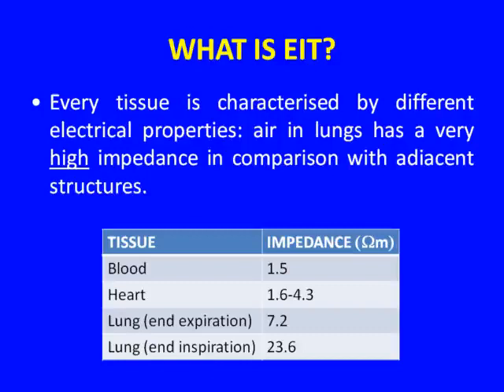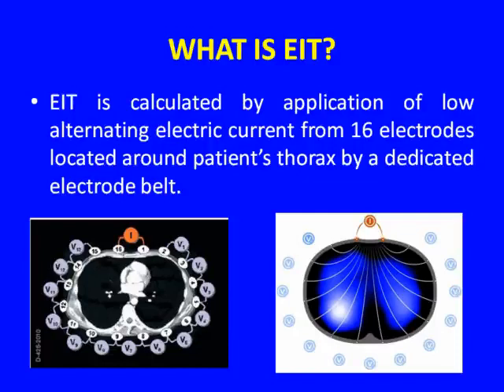From a physician's point of view, in the thorax there are different tissues with different electrical properties, and air in lungs has a very high impedance to electricity. Starting from this concept, EIT applies alternating electric current from 16 electrodes placed around the patient's thorax with a belt. Current is applied between two electrodes while the rest of the electrodes register the signal coming from this current.